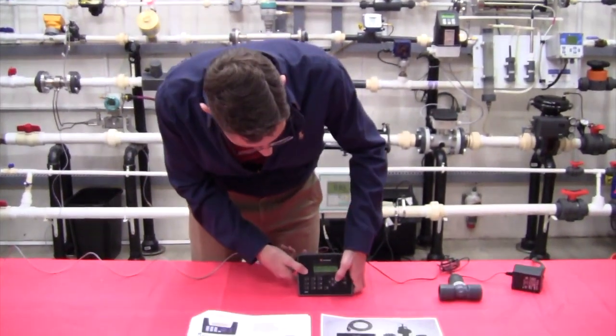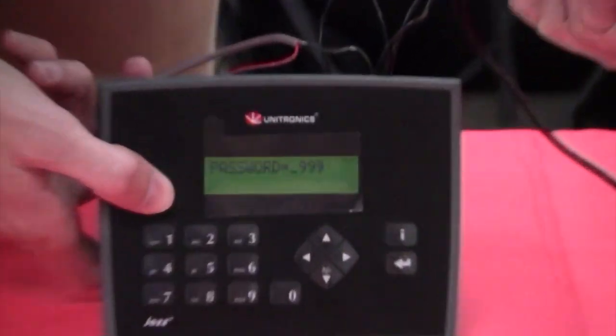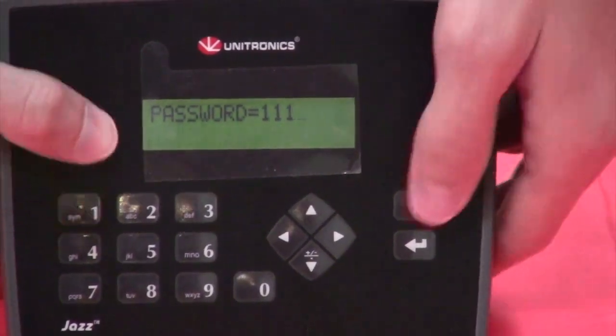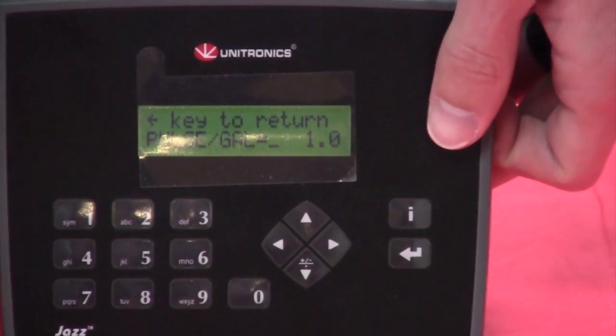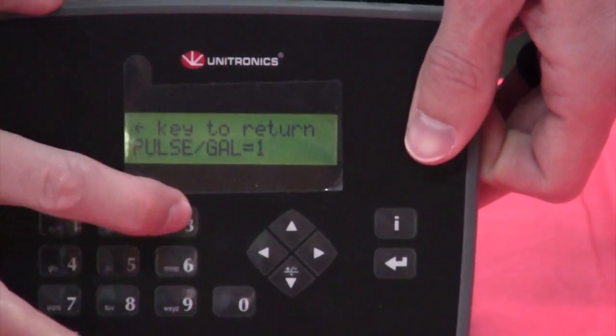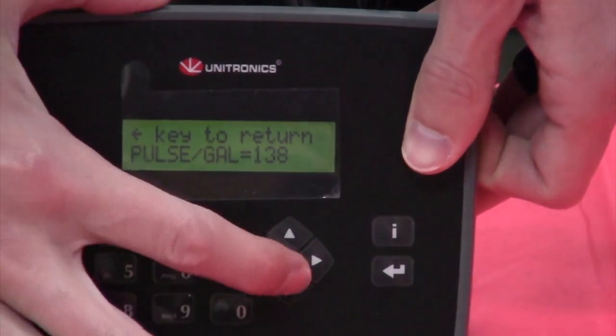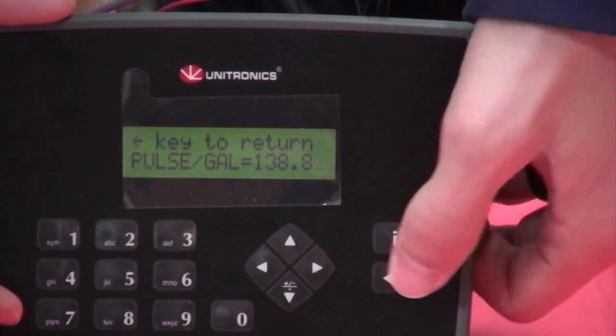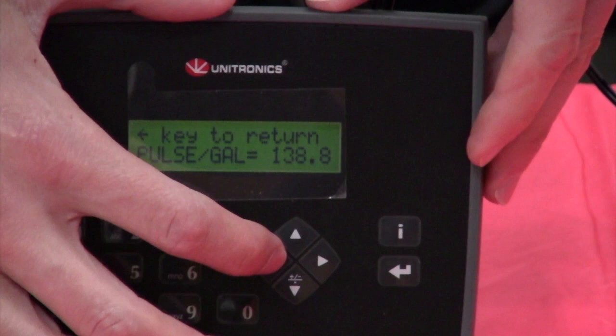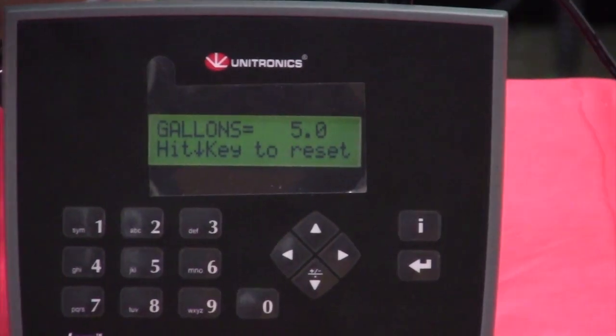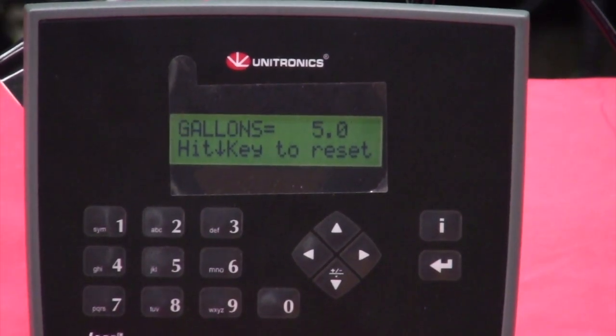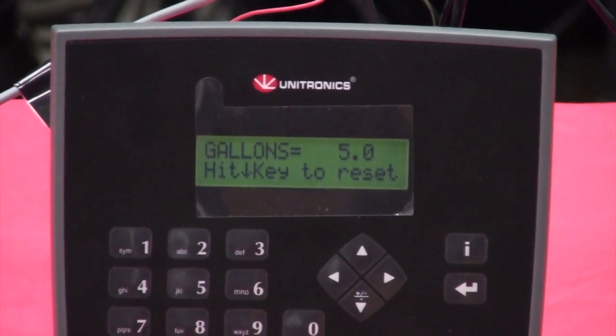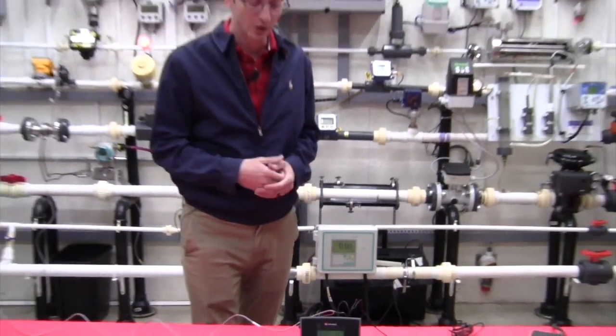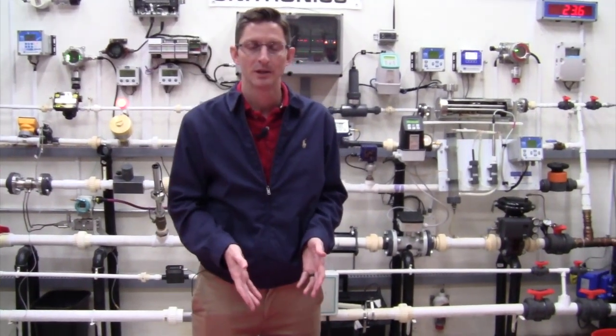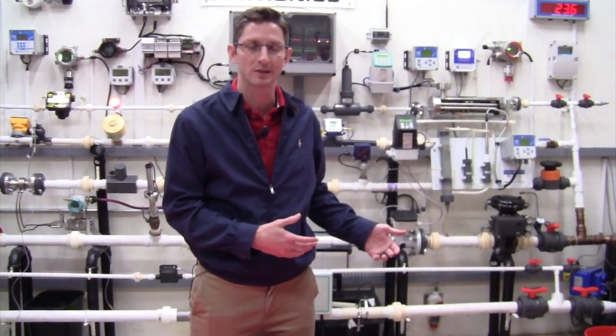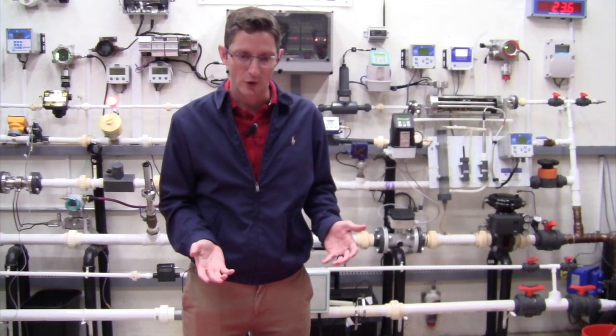So I simply come back into the meter, press my up arrow, 111 for the password, enter button, and here I'm going to type in 138.8. Hit enter. Hit my left arrow to go back out to the main screen, and now I show a total flow of 5 gallons. That's it for your calibration. I personally recommend that you do this 3 times. Take the average across those 3 buckets. That's what you need to do for a calibration.